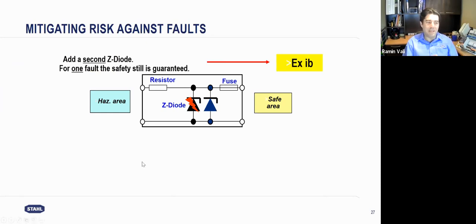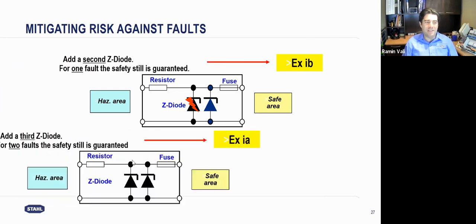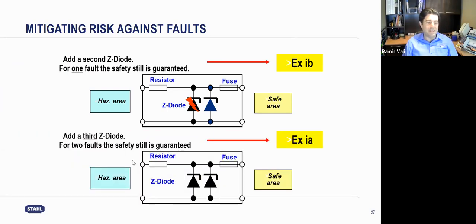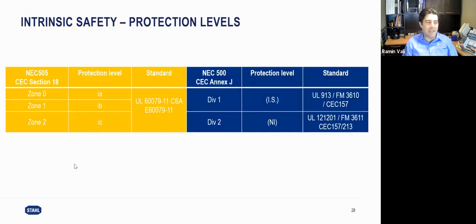And that means this barrier can have one level of fault tolerated, and the system is still safe. If we have additional Zener diodes, for example, in parallel to the other two Zener diodes, and if two Zener diodes become faulty, then we have a third Zener diode still working and provides that safety feature which we need in the field. So that 3 or 2 level of fault tolerance will be indicated in our code as EXIA or IB or IC.